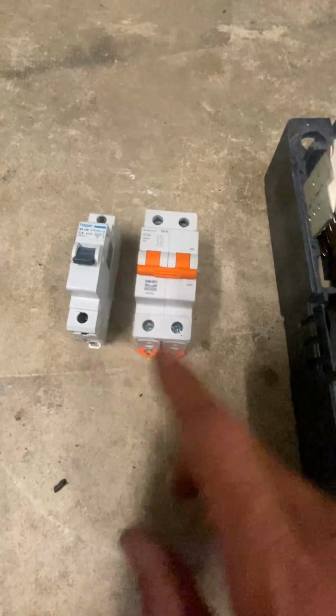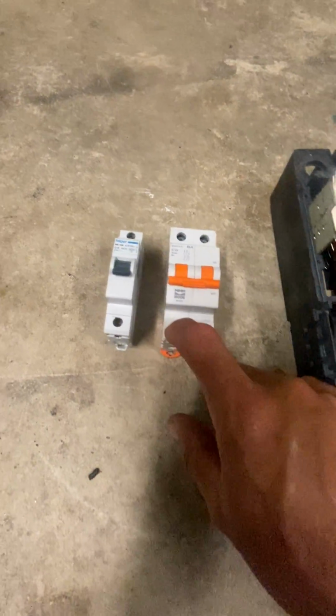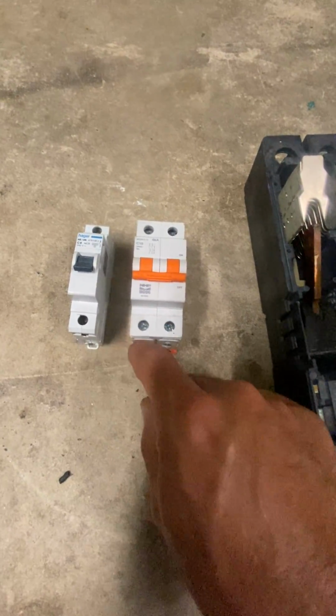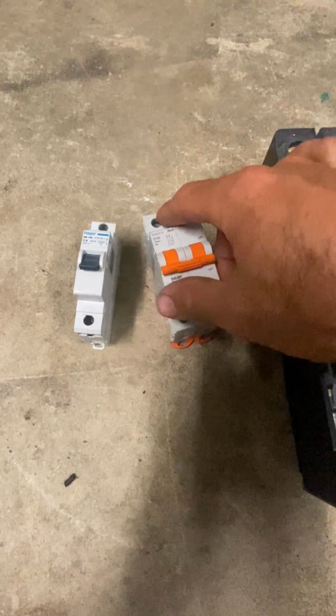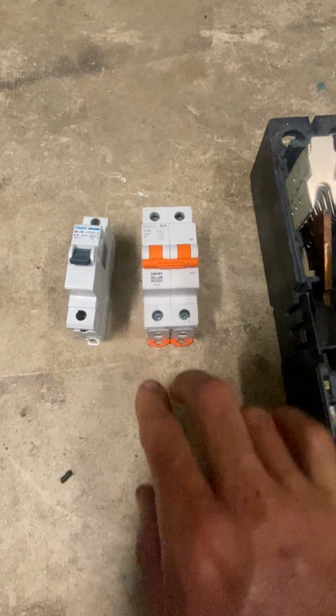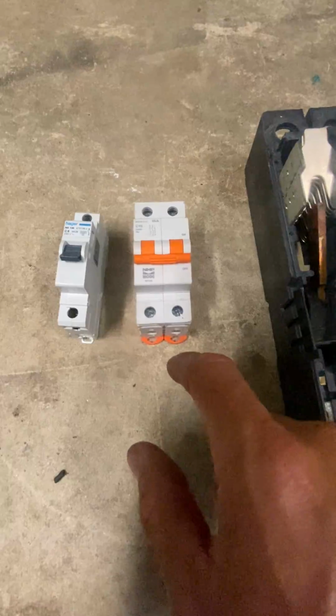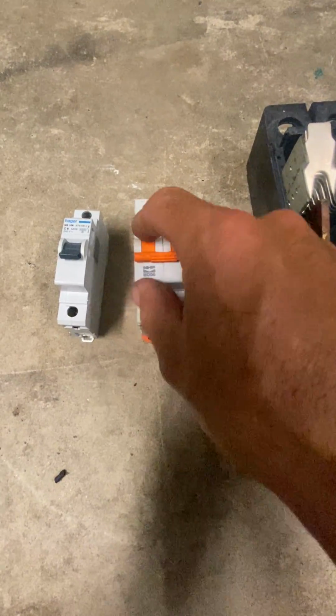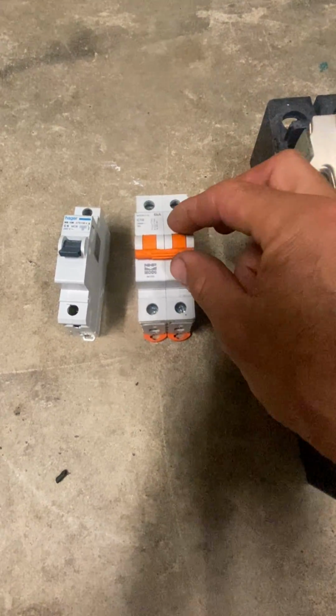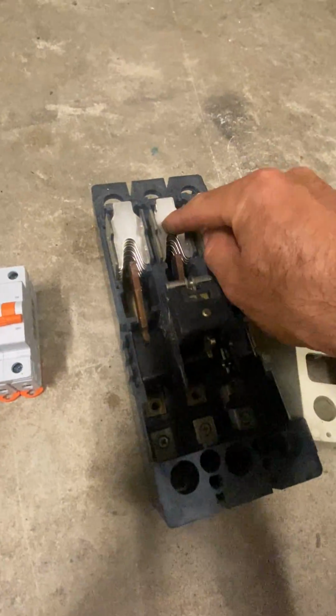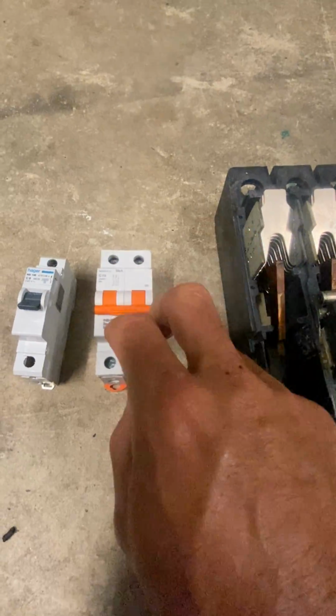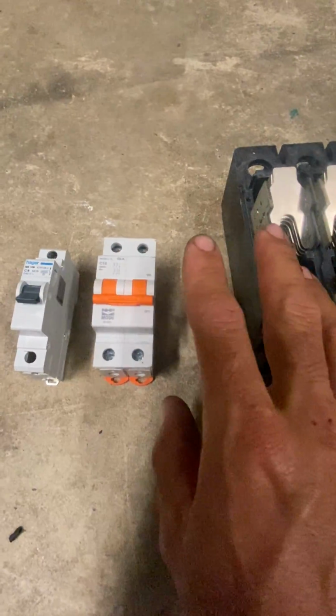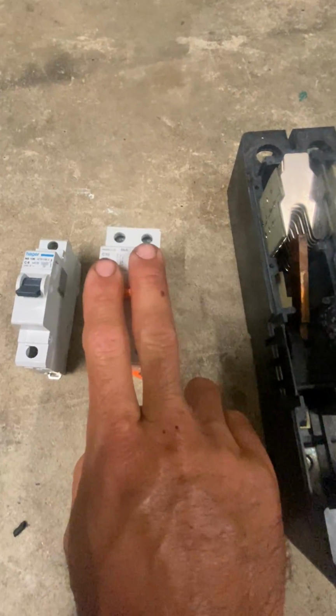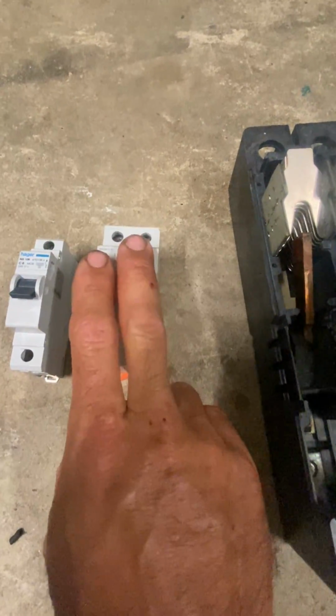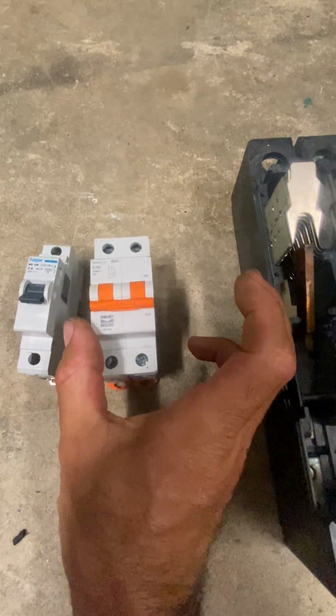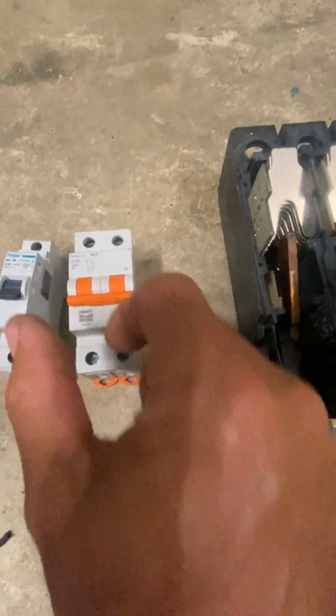And normally with a lot of the dedicated DC circuit breakers, in some applications they'll get you to wire the incoming that way, then loop it over here, then come out there. So basically you're using the same breaker to break the one effective circuit, because when it goes through there you get a distance of X, and as you loop it back through, that's 2X. So you've doubled the breaking distance of the circuit breaker. Normally in DC they'll have 2-pole and 4-pole applications for higher voltage applications, and each pair will do one polarity, positive, and the other will do the negative. It's common in solar applications to use 4 poles, and they'll be looped through.